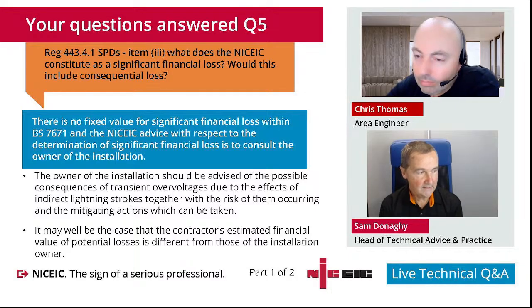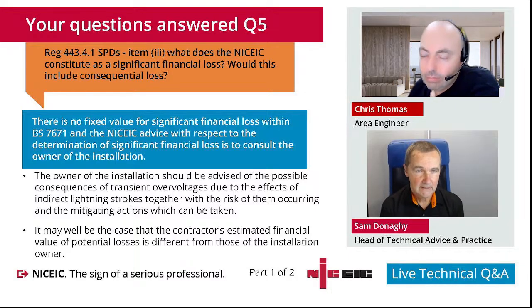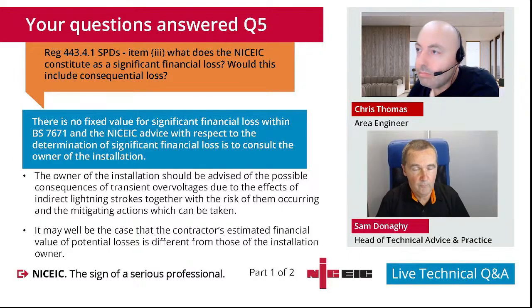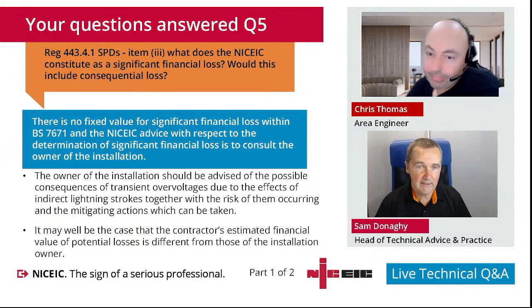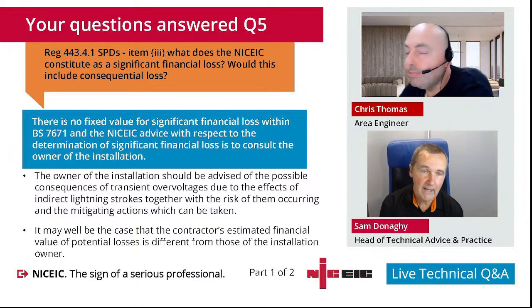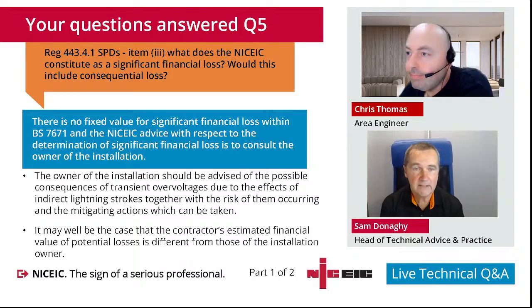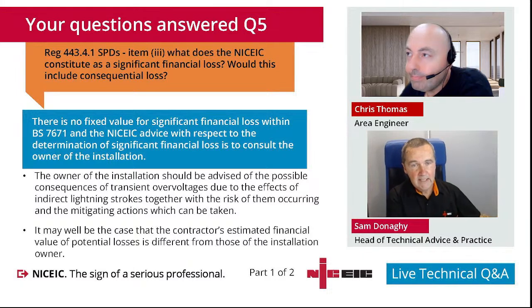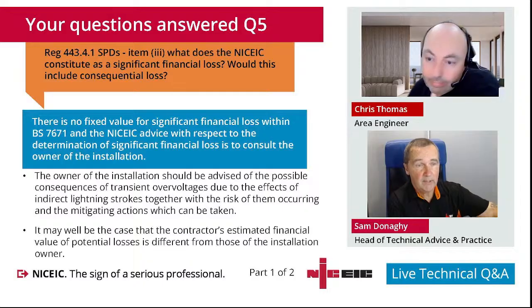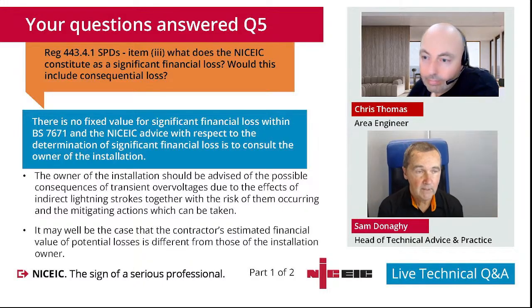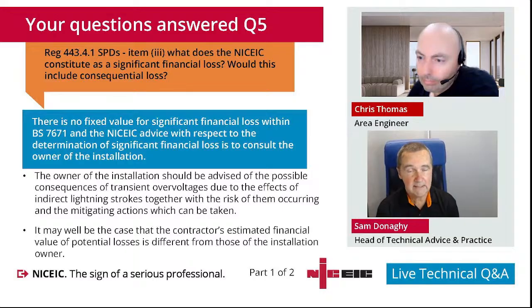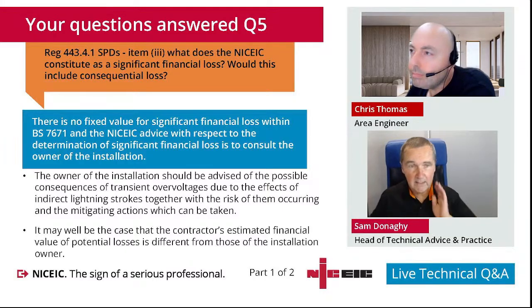A couple of things to say on that. The first is that there's no fixed value for what is termed significant financial loss, or what the threshold in monetary value would be within 7671. And we always advise that with respect to the determination of what is a significant financial loss is to consult the owner of the installation, because what we may consider significant, they may not, or vice versa. What value we may not consider, they may consider. So it should be determined by the customer.